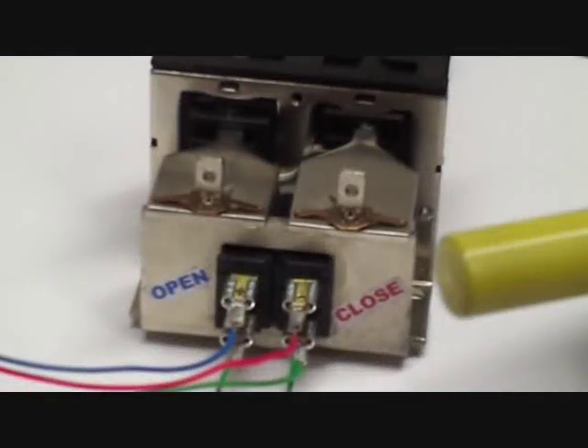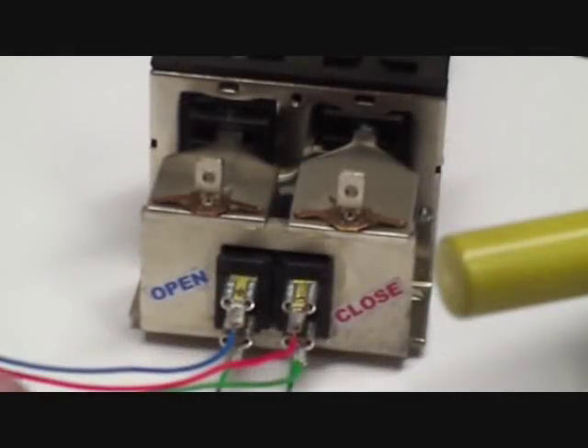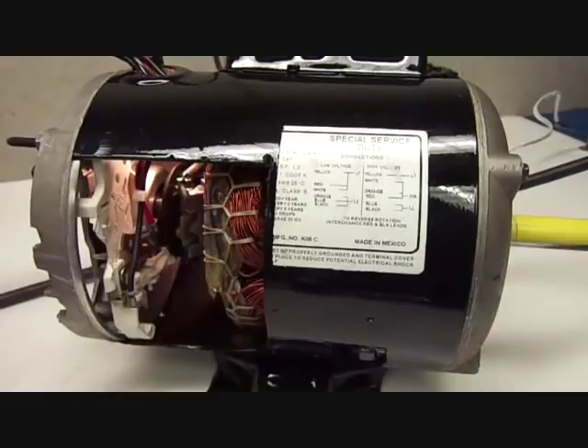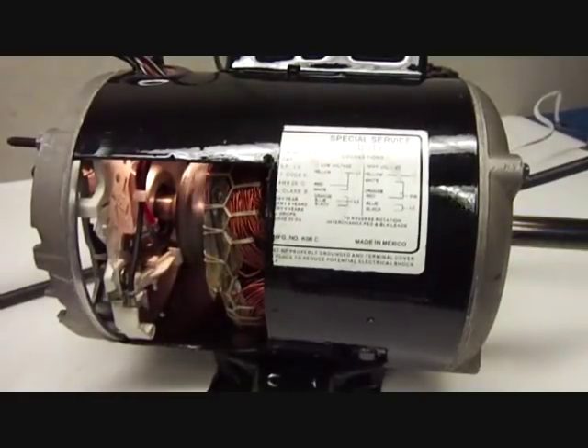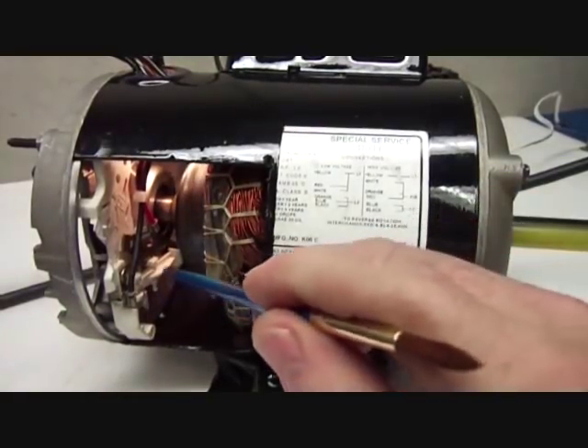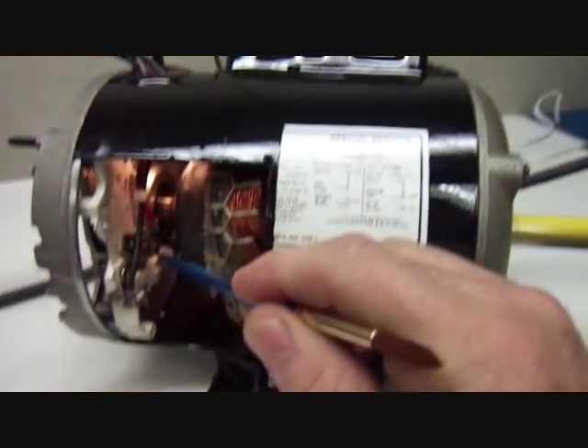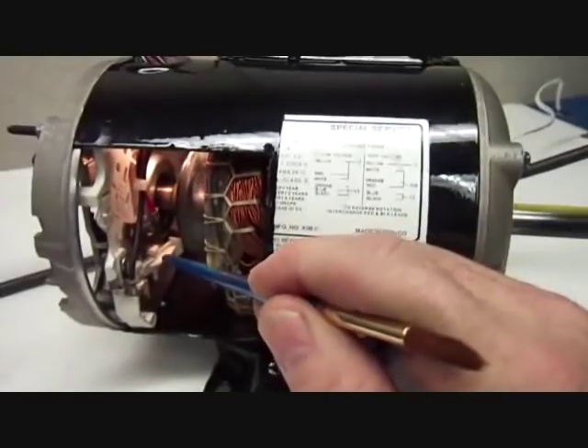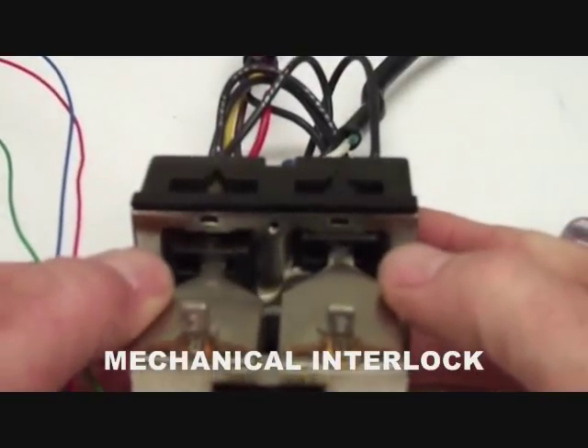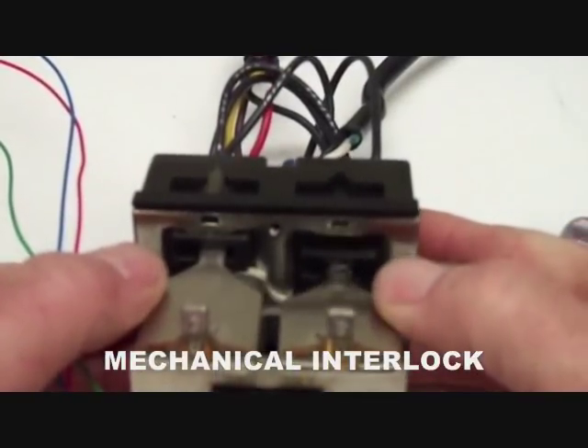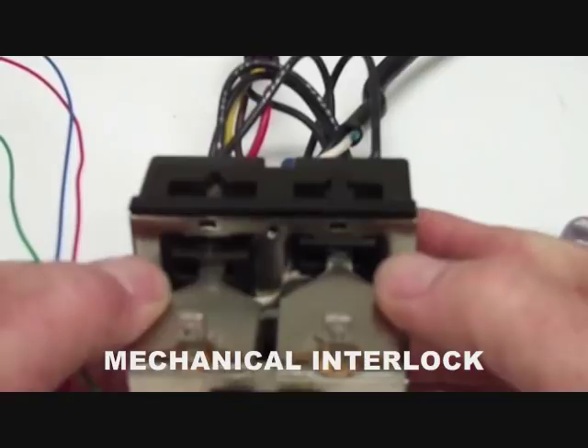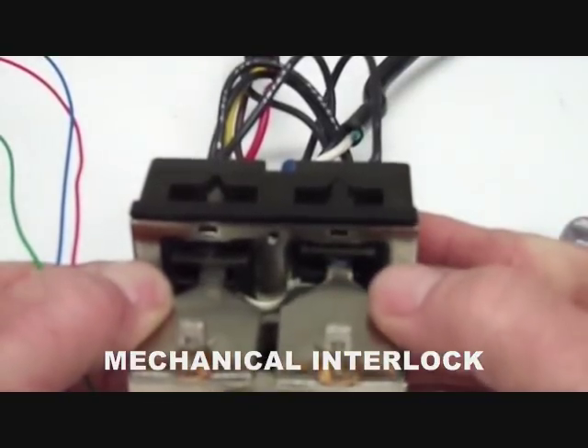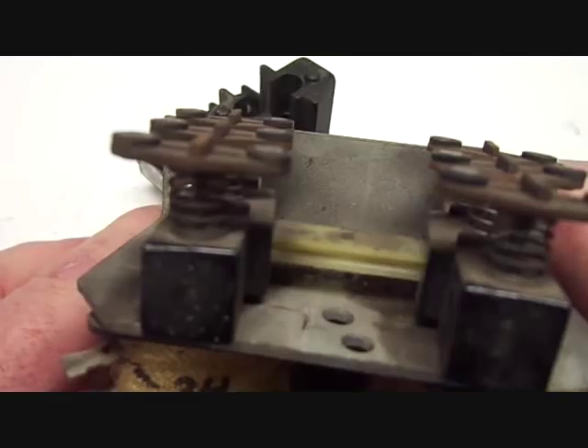So how about those interlocks? Like I said, it's really bad to try and run a motor both directions at once, and it only takes a few seconds to ruin a motor. So these contactors all have mechanical interlocks that kind of work like a seesaw. They make it impossible for both sides to pull in at the same time.